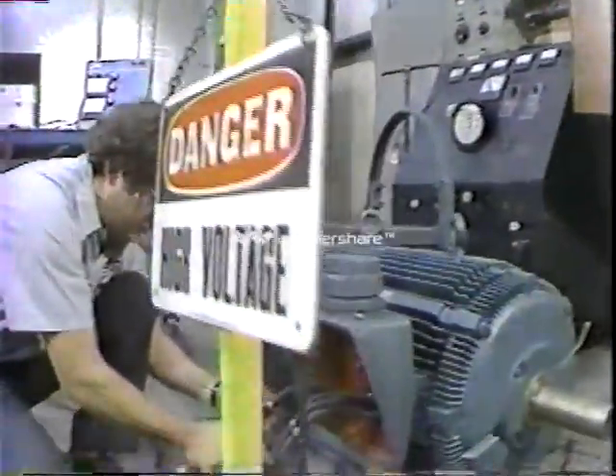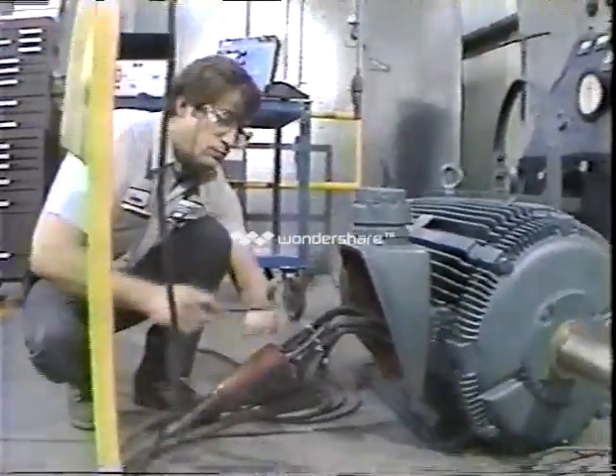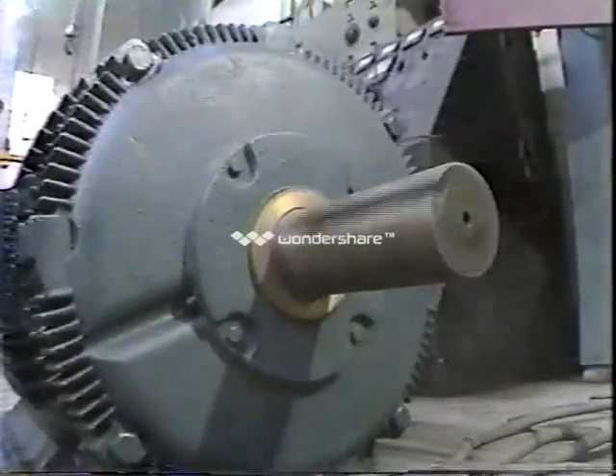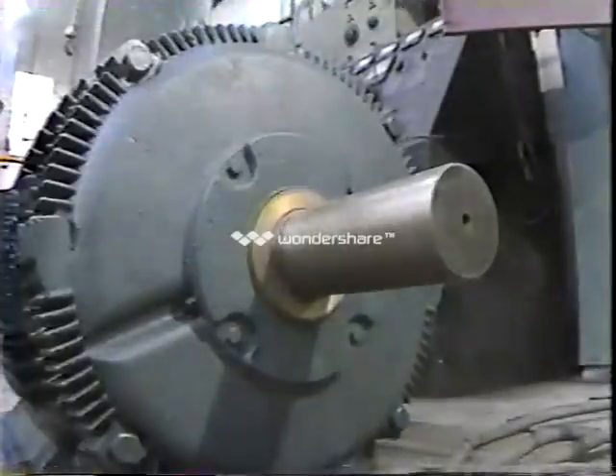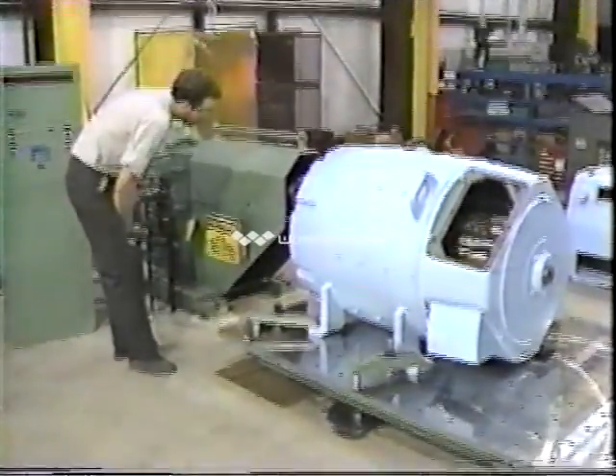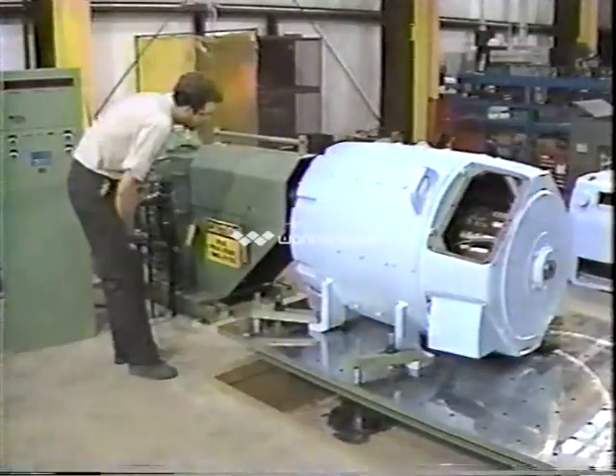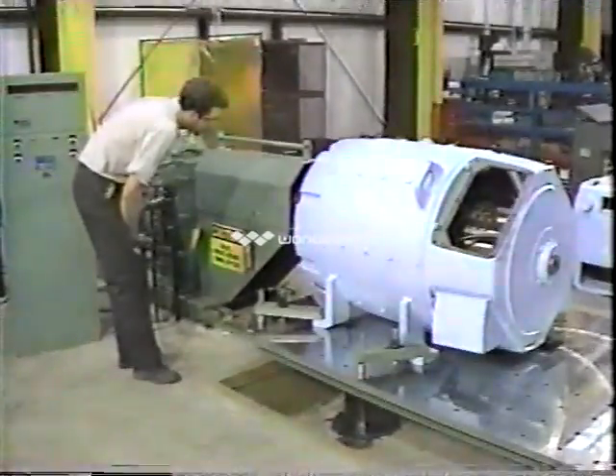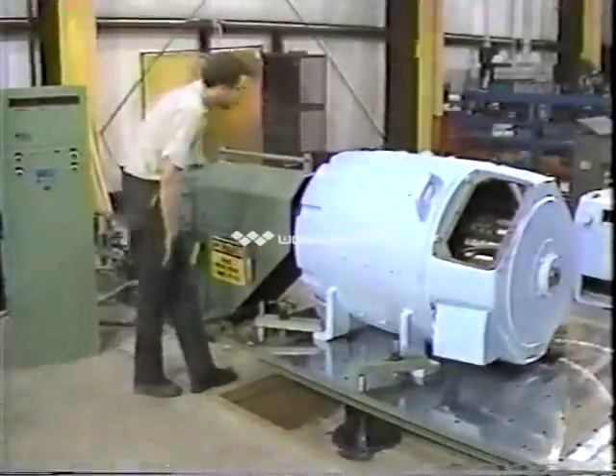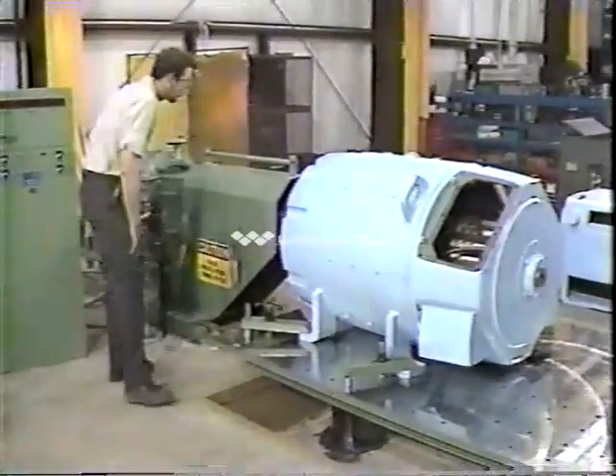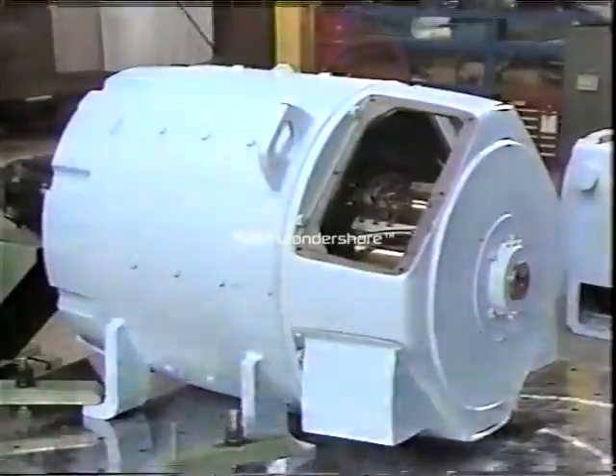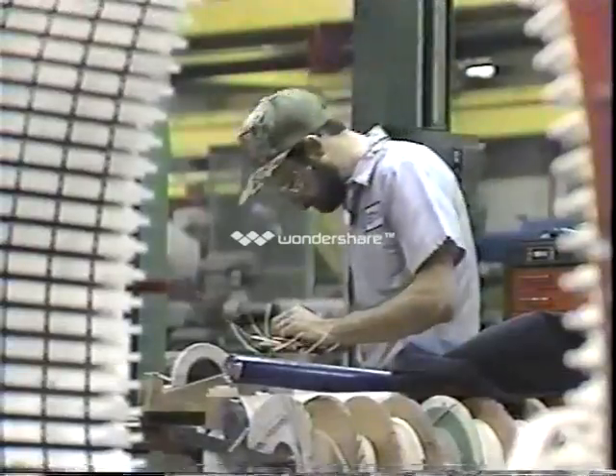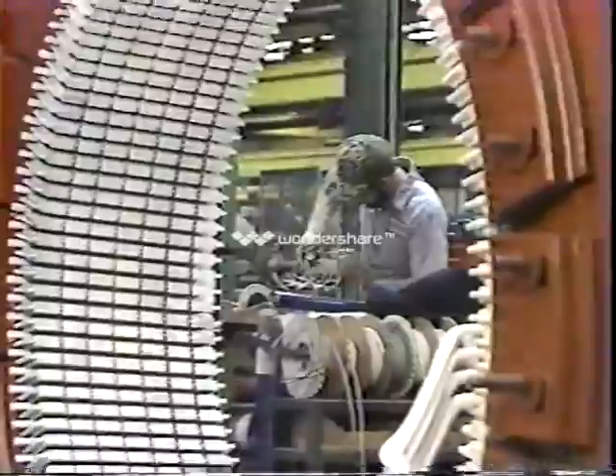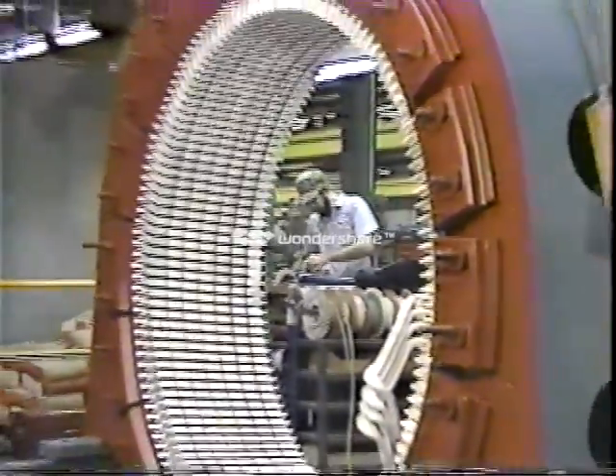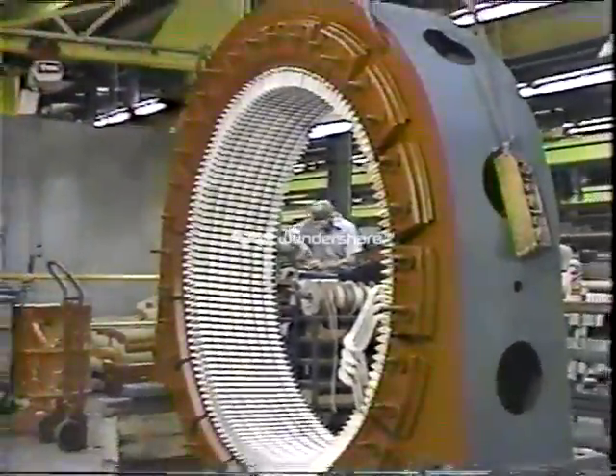Next is the running test. This is where we apply the voltage for the first time in order to make sure the motor can handle the required voltage and can achieve the rated speed. Here we also check the assembled motor again for vibration. Our final test is the load test. We can dynamometer load test up to 1,000 horsepower, applying a load that simulates the actual working conditions of the motor. Vibration and overheating is also checked to ensure that your motor comes back to you ready for service. As you can see, a lot goes into repairing your motor at Ingleside Electric. A lot of quality work and a lot of attention to detail spell out a job well done.